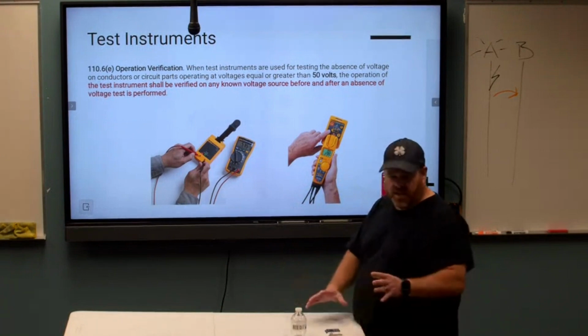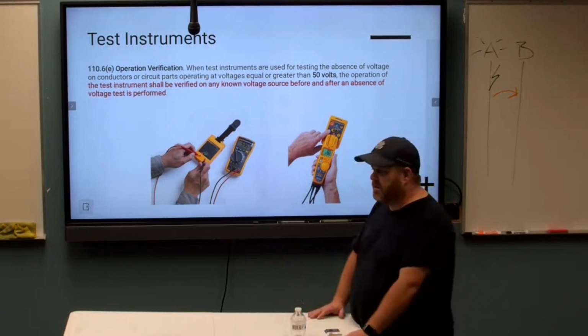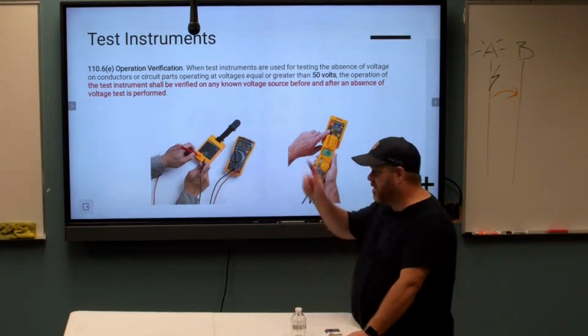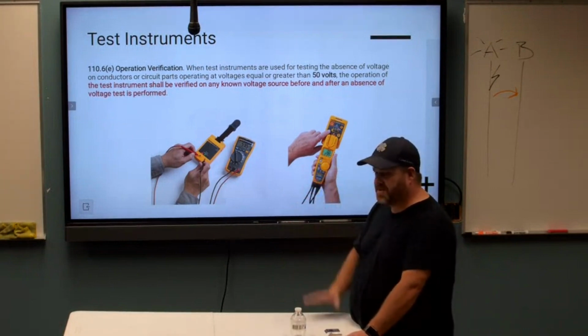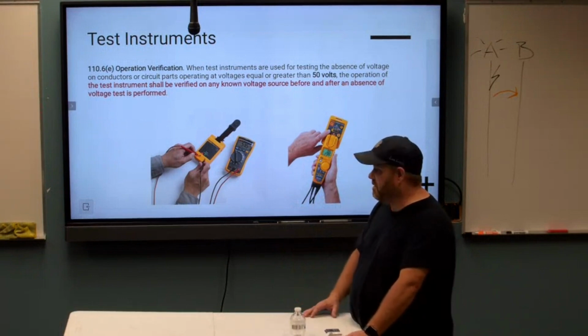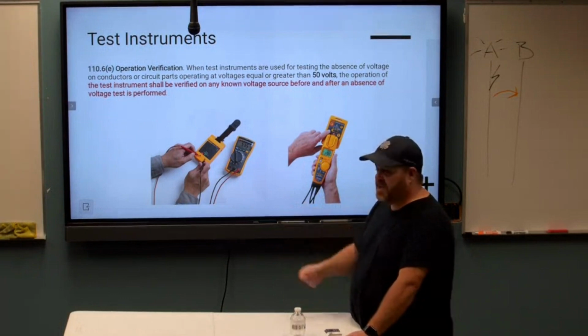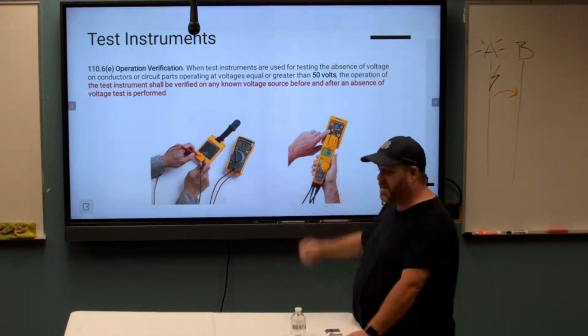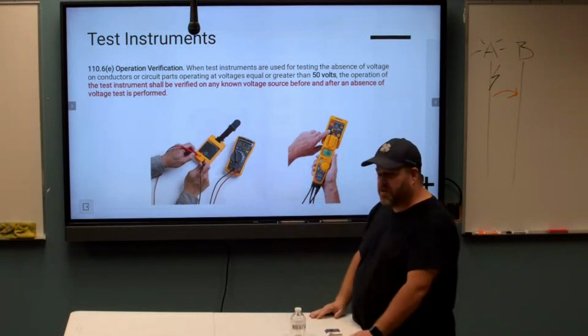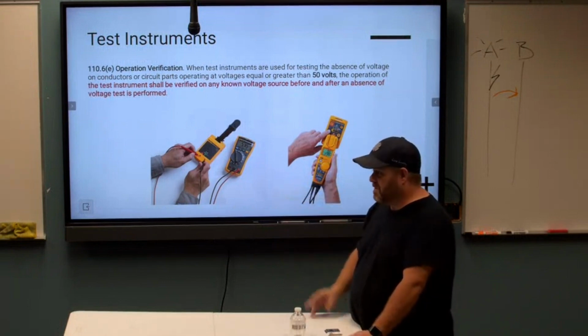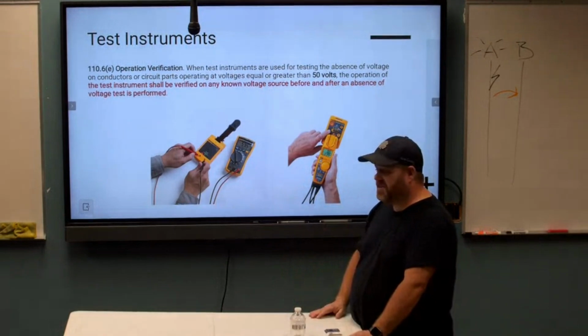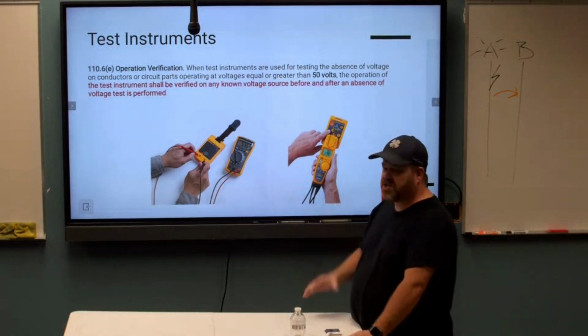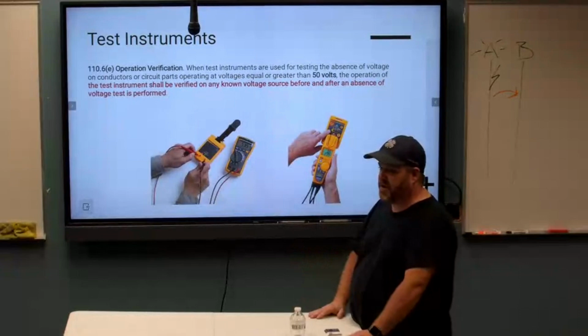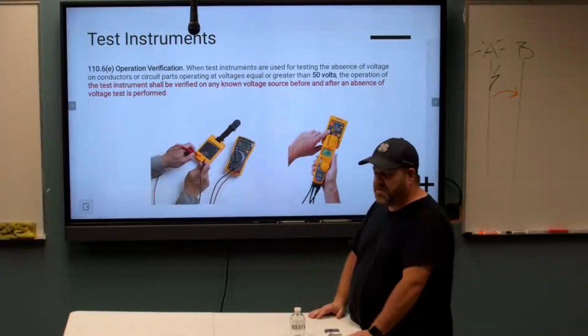It's good to get a deal, but don't go to Harbor Freight and buy the one that says industrial strength with diamond plate box styling. There have been people who literally died using those because of a transient spike in a fraction of a second. In one case back east, a guy was testing a 480 volt circuit in a mall and there was a spike—in just a fraction of a second the meter blew up, caused an arc flash, and killed him, along with the fire marshal standing right behind him, because he was using a cheap meter.